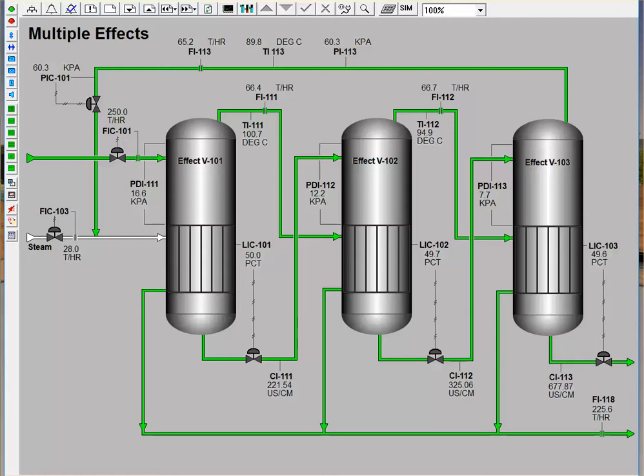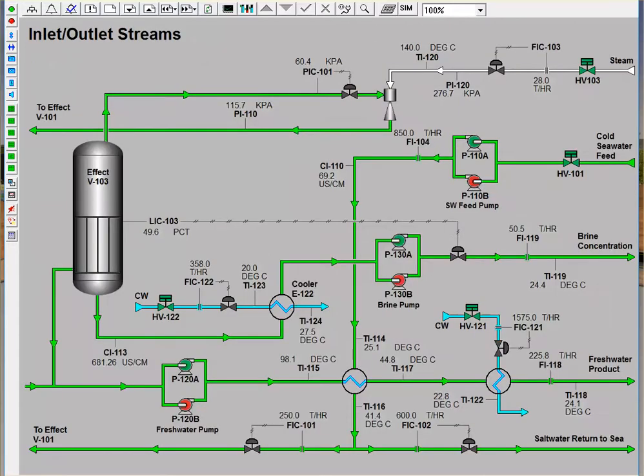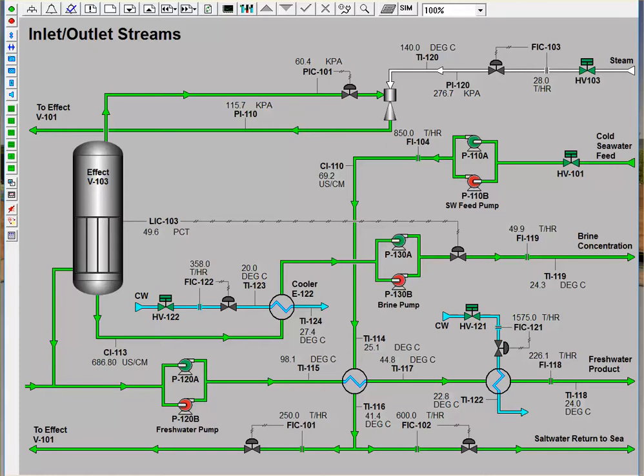Now we will move to the third schematic and see in more detail how the different inlet and outlet streams are handled prior to and after passing through the three evaporators. Before the concentrated brine leaving the third evaporator can return to the ocean, it must be cooled to an appropriate temperature. Therefore, it is important to note that this brine passes through a cooler prior to re-entry into the ocean. Cold seawater is pumped from the ocean at a rate of about 850 tons per hour and at a salinity of about 69 microsiemens per centimeter. To increase efficiency, both this stream and the freshwater product stream pass through an exchanger to cool the freshwater product and preheat the feed prior to entering the first effect.